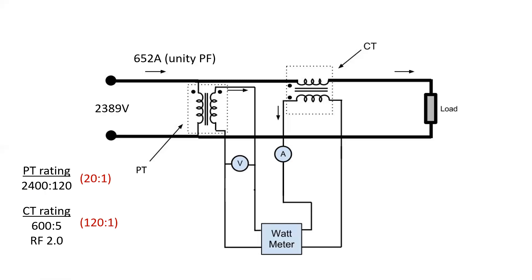At this point, what we're going to do is calculate what the voltage is on this voltmeter. So, we've got 2389 volts and a 20 to 1 PT rating. So, if we're familiar with ratios, it means that we're going to take 2389 and divide it by 20. So, that means that the voltmeter, which is on the PT secondary, should be registering about 119.45 volts. The CT is connected to an ammeter. What value is the ammeter reading? Well, it's 120 to 1 and it's 652 amps. So, 652 divided by 120 gives me 5.43 amps. So, the ammeter is registering 5.43 and the voltmeter is measuring 119.45.